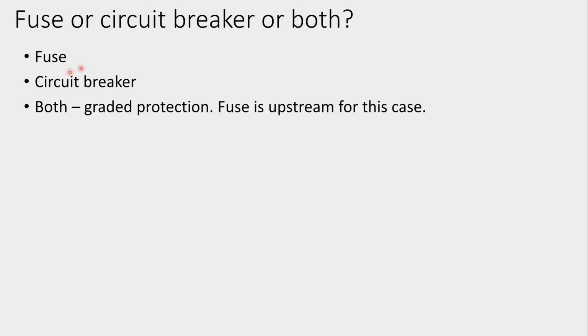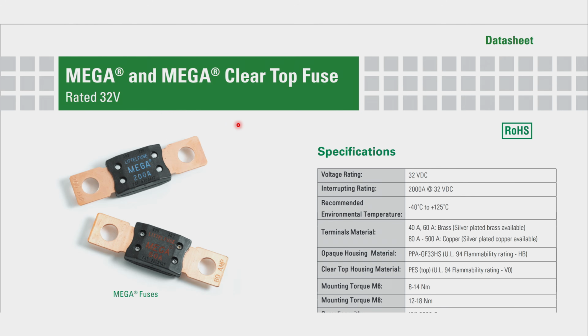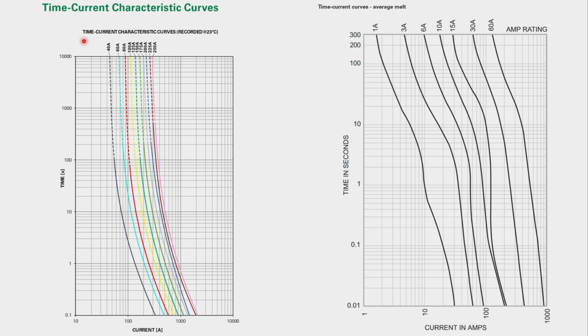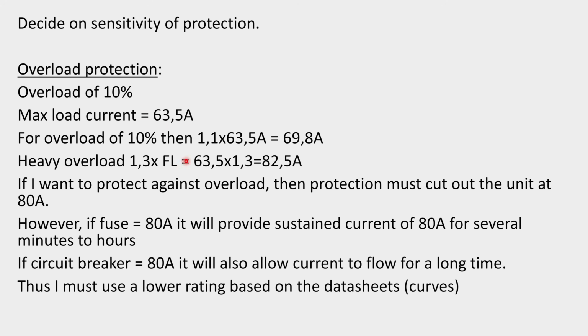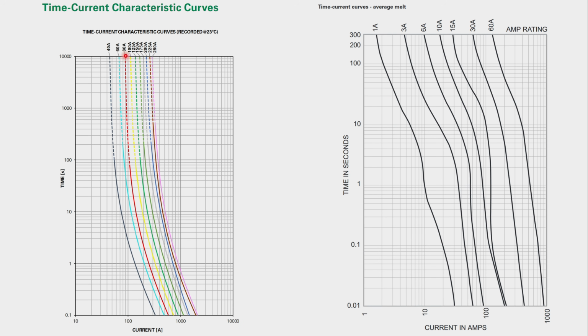So let's first have a look at the fuse. Now here's an example of a fuse, and let's look at its melting characteristic. All right, so this is the time current characteristic curve for different amperage fuses. Now let's look at an 80 amp fuse. Now the reason why I've chosen 80 amps is because earlier I worked out that if I'm protecting for a 30% overload, the current must cut out at 80 amps. So if I had to use an 80 amp fuse, it's this dotted red line here. Notice that this is 100 amps, this is 90, so this is 80 amps over here. It's this line over here, and it goes all the way to there. Notice that the 80 amp tripping line does not actually cross over the 80 amp load current line.